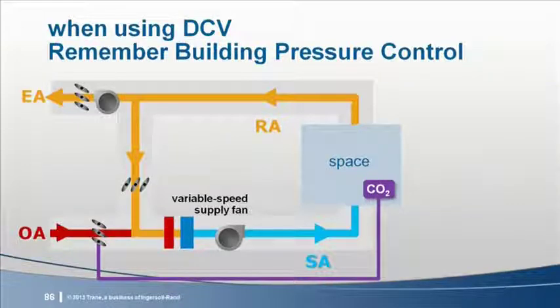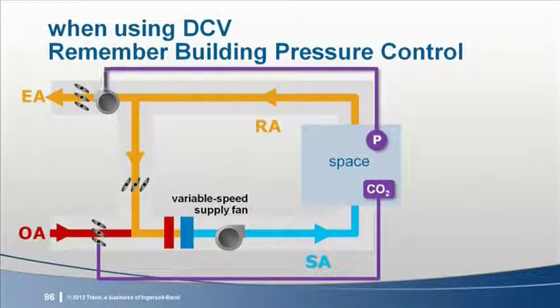And if you do implement demand control ventilation, don't overlook that you probably need to provide some method to reduce exhaust airflow too. This prevents negative building pressure when demand control reduces the intake airflow.